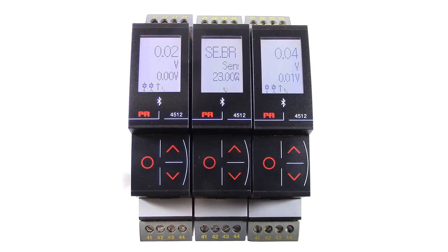se.br appears on the display, and scrolling help text helps you to understand the nature of the error. Also, the backlight blinks to help you spot an error among a group of products mounted on DIN-Rail. A sensor break error occurs if the sensor has failed, the wrong sensor type is connected to the module, or there's no sensor connected to the module.